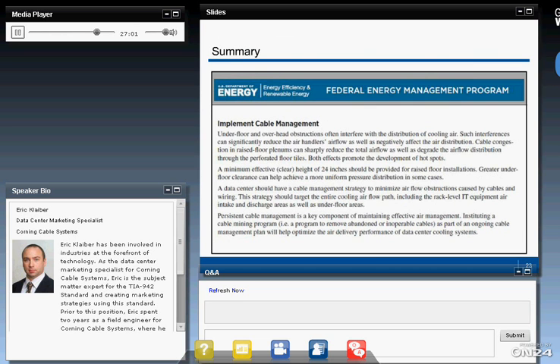So here's the last thing we want to sum up with. This is from the U.S. Department of Energy, or the Federal Energy Management Program. Here's where it states that a minimum effective clearance of 24 inches should be provided for all raised floor installations. You need to have a cable management strategy to minimize the obstruction of airflow throughout your entire data center. So you need to have this strategy put in place when you're designing the airflow. And you're designing the actual overall data center, how many CRAC units you need, how big those CRAC units need to be, what your chiller temperature is going to be. So there's a lot of things that go into not only deciding between copper and fiber. Again, the fiber has the lower per-port wattage, and the fiber itself, even though there's loss occurring, doesn't create heat, whereas copper does. So the less copper you have in your data center, the smaller the CRAC units can be, slightly.